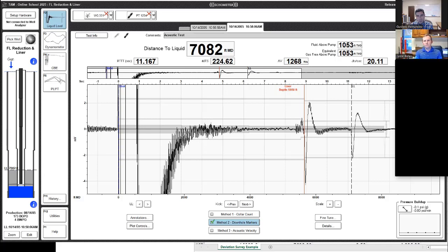Yeah, that's a good point. We will need to understand more what type of well they are talking about. Are they able to manipulate the pressure by injecting or bleeding some of the pressure, monitoring the other side? If it's through a single shot, you have mentioned, Justin, that you only have a 15-minute window of pressure data collecting. If it's just using the liquid level single shot method, or if you have a plunger lift license, your well analyzer, or wireless base, then you could use a plunger lift module to have a longer pressure track in either the tubing or the casing. So it could be done. There are special techniques that are used to identify tubing casing leaks, and that'll be covered in 2 days. So stay tuned for Thursday.